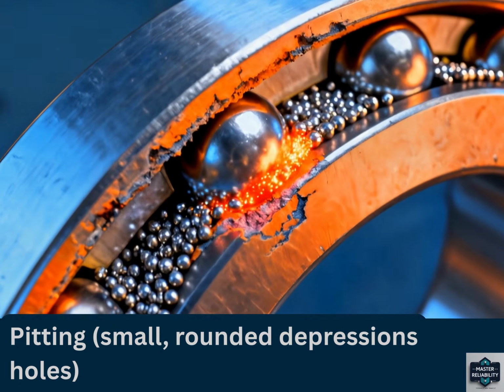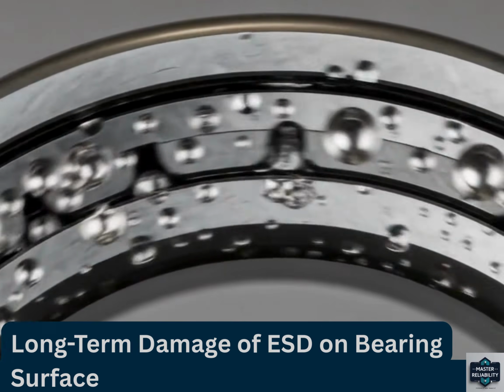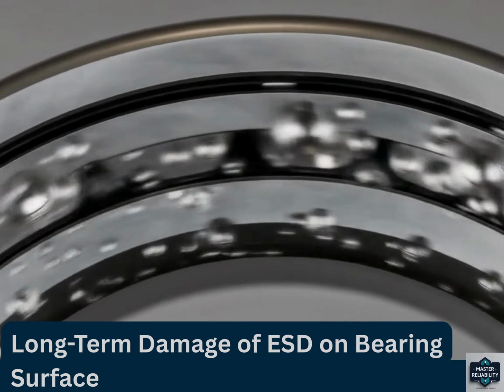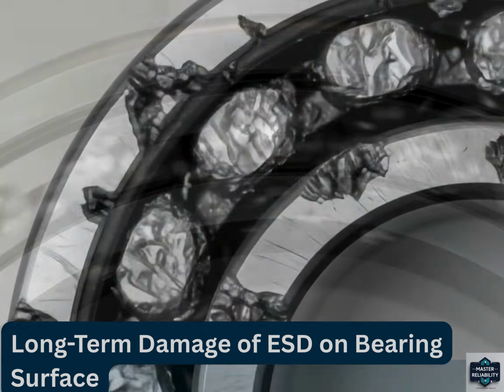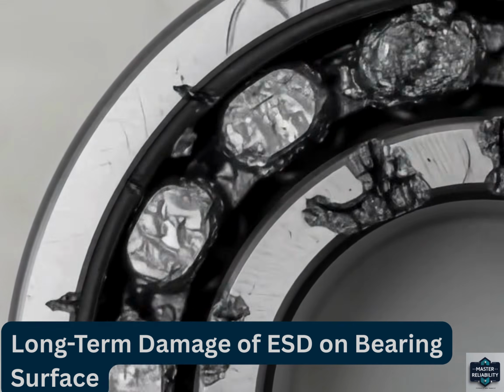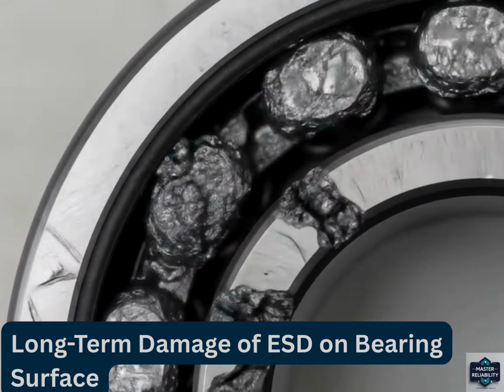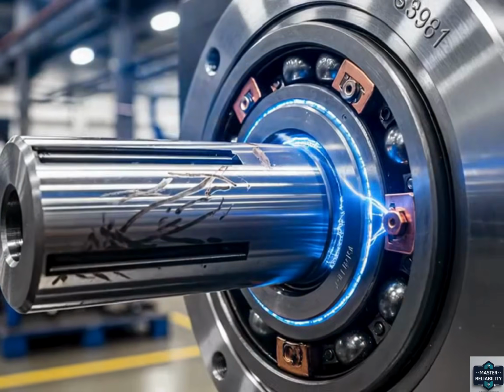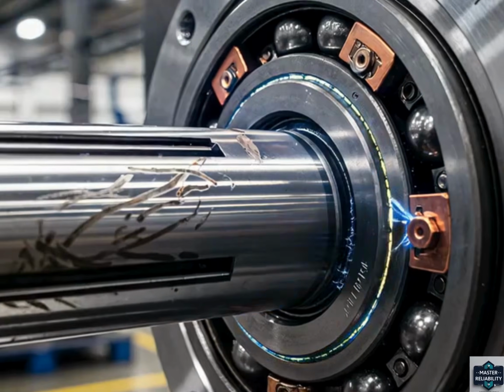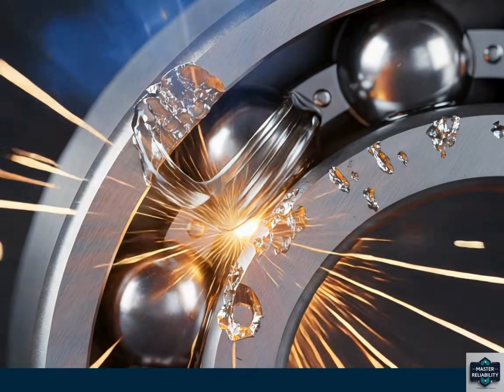Over time, repeated discharge events link isolated microcraters into continuous fluting and pitting patterns, increasing vibration and noise and significantly reducing bearing life. This failure mechanism can escalate rapidly during operation, especially in dry or high-static environments.